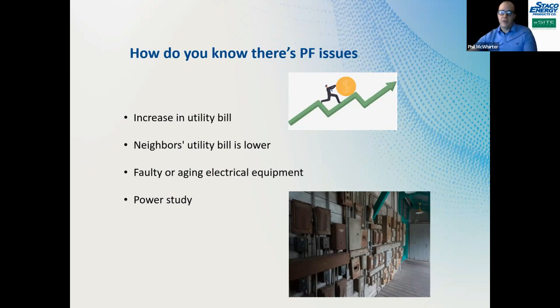Maybe you have a facility that's the same size as your neighbor's, and you're talking to one of the facility engineers there about your utility bills, and you realize that their utility bill is much lower than yours. If it's the same size, the same load and the same demand, what's going on? Why would your utility bill be higher than your neighbor's? Well, maybe you have poor power factor. Again, faulty or aging electrical equipment is a big cause of power factor issues.